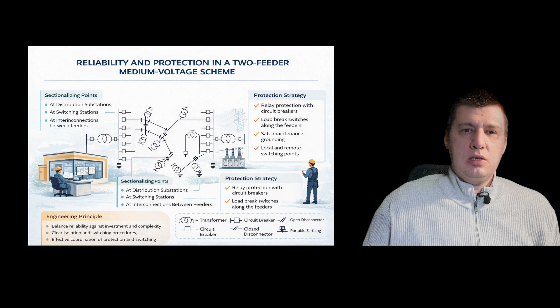Now we analyze reliability and protection in the two feeder medium voltage schema. Supply reliability is higher in the two feeder configuration. Consumers can receive power from the same primary substation through different busbar sections, or from two different primary substations. In more advanced configurations, even four substations may participate, so the load is supplied from the nearest available source. Sectionizing points are located at the distribution substation, a switching station, or at interconnection between neighboring feeders. Distribution substations often have two transformers. This allows additional reserve capacity at a low voltage level.